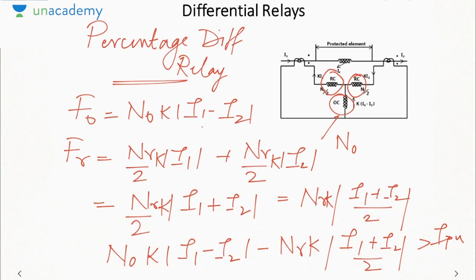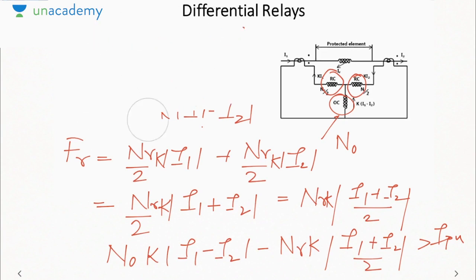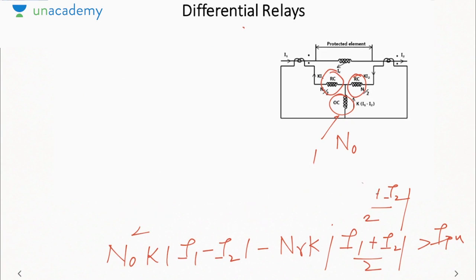So that way we have increased the pickup value, or we have increased the condition on the difference between the two currents. I will tell you an example. Here, let me first tell you about the two terms. The NR by N0 term here is called the bias or slope of the relay.